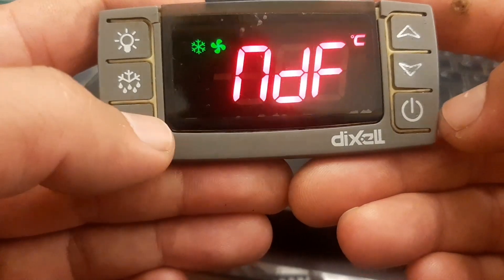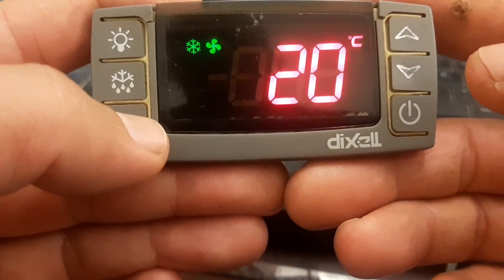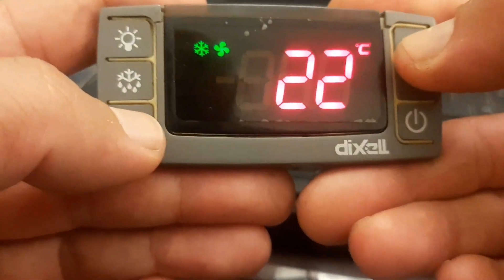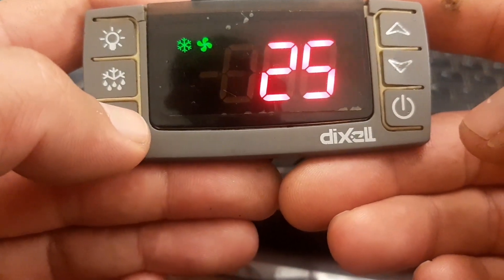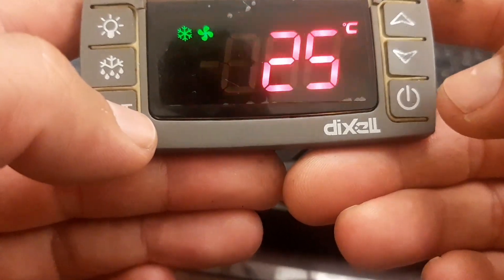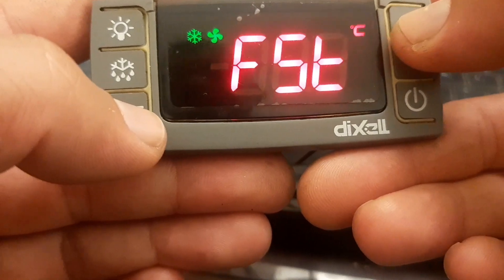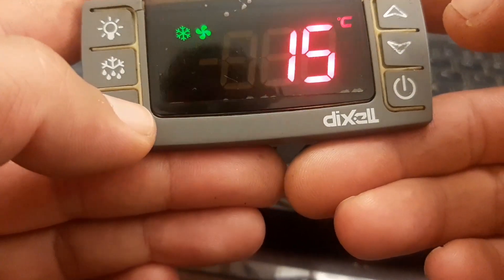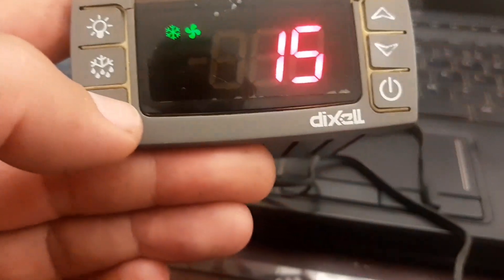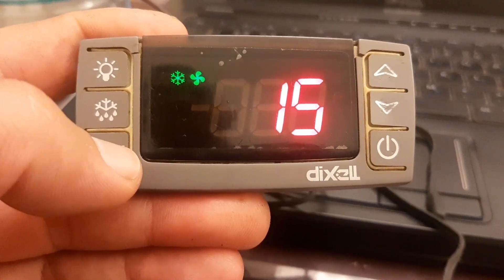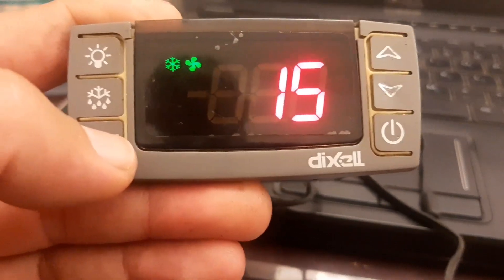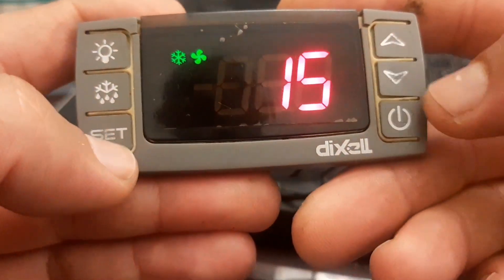Then NDF is the maximum time your defrost will run. For example, I set it to 25 minutes, so my defrost will run for 25 minutes. After 25 minutes, defrost will terminate. However, the DTE temperature setting also applies - if your evaporator temperature reaches 15 degrees in 10 or 15 minutes, defrost will terminate before the 25 minutes is up. That is how you configure the defrost settings.